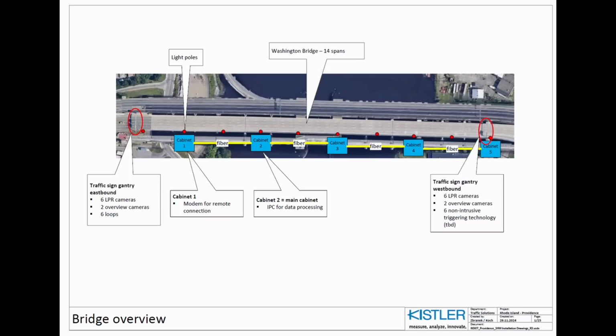So why would they pay in full if the system's still being calibrated? You've got all these sensors across the bridge. When you calibrate it, you take a truck of known weight and drive it across the bridge and watch your sensor readings. Based on the size of the member being instrumented and the load imposed, you should be able to calculate the strain readings and compare that to the measured strain readings. If adjustments to a calibration factor are needed, you can do it at that time. But that process shouldn't take months and months based on my understanding of these systems.